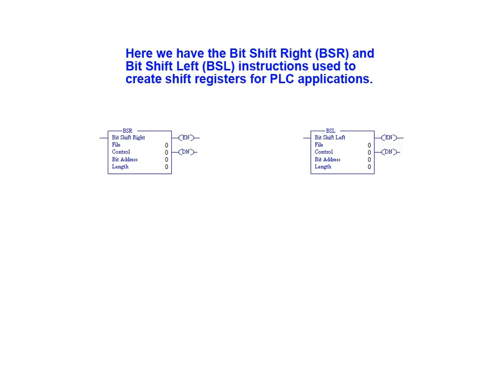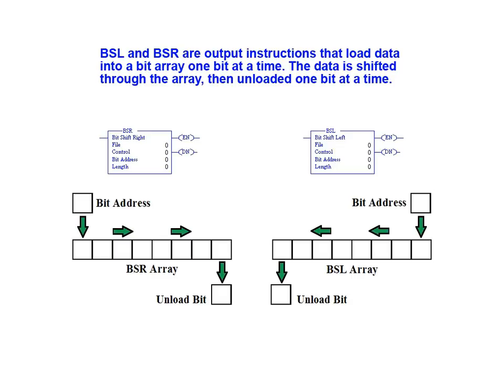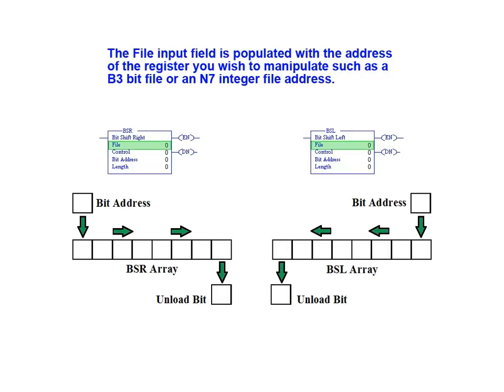Here we have the bit shift right and bit shift left shift register instructions. BSL and BSR are output instructions that load data into a bit array one bit at a time. The data is shifted through the array and then unloaded one bit at a time. The file input field is populated with the address of the register you wish to manipulate, such as a B3 bit file or an N7 integer file address.